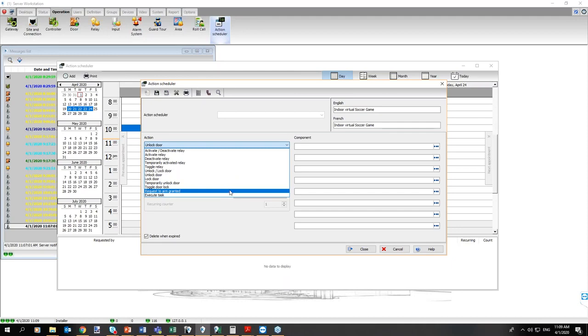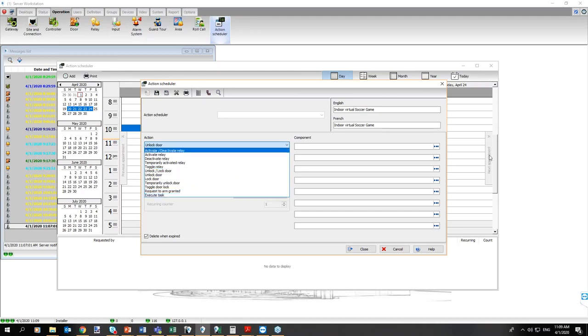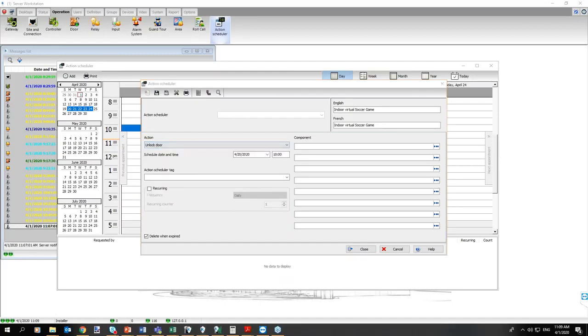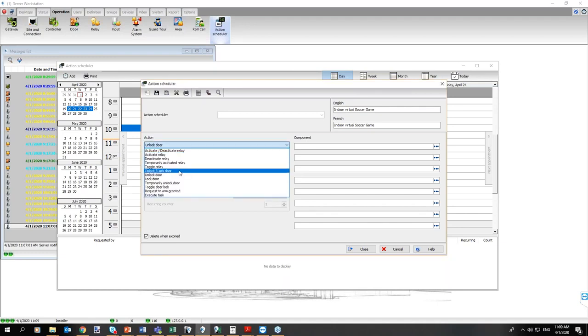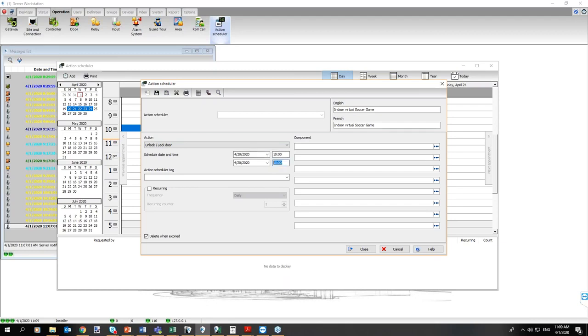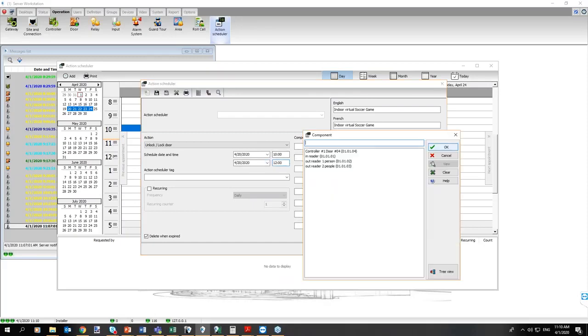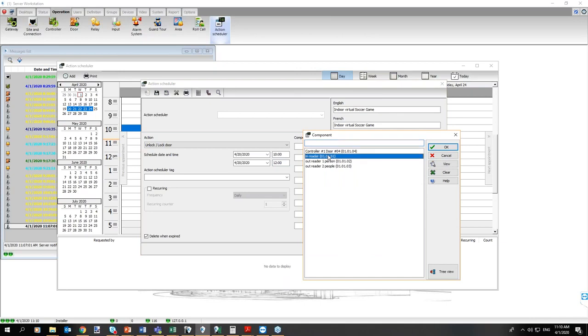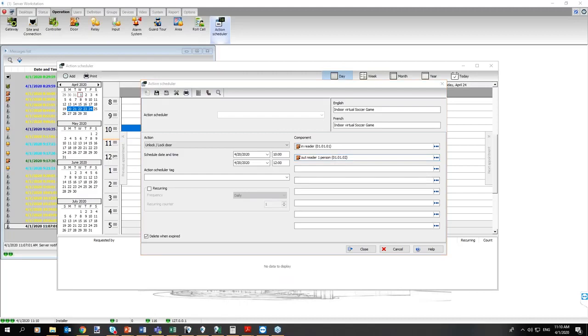The cool part is I could do an auto-arming schedule if ever wanted automatically. I could also use a new command that we've added called the unlock and lock command. The unlock and lock command is kind of a hybrid which allows me to schedule a start date and an end date. For example, unlock at 10 a.m. until 12 p.m. This gives us the ability to choose two hours. Then I could single-handedly choose any eight doors in this example from any controller. It's not dependent on the controller.